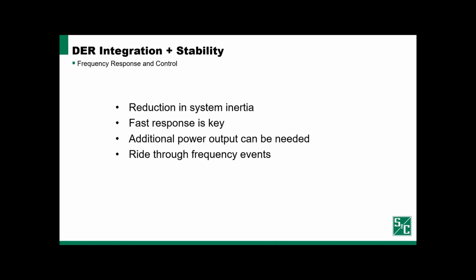Frequency response is also key here. There's a reduction in system inertia as inverter-based resources displace rotating machines. Rotating machines have a large rotating mass that helps provide inertia to bulk power systems. This rotating mass can help correct for mismatches between prime mover supplied power and instantaneous demand.